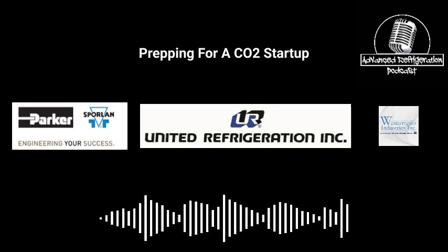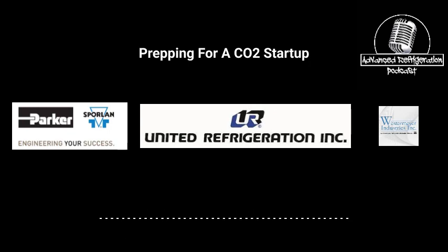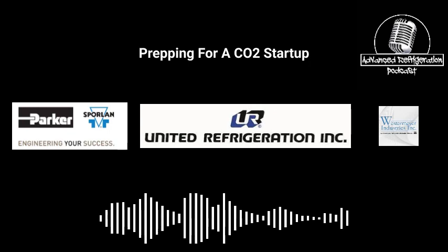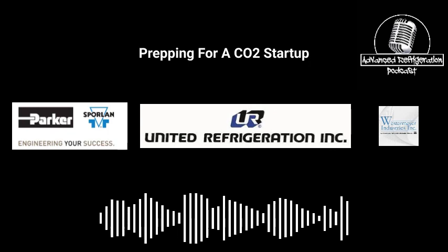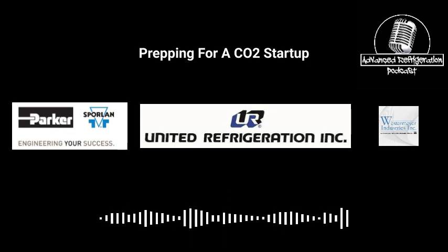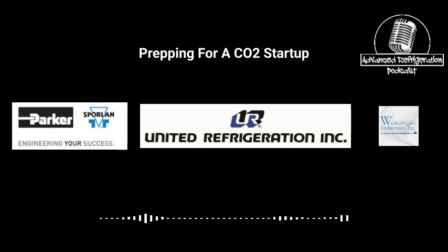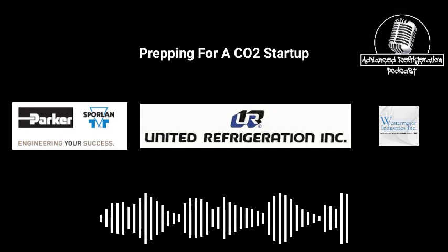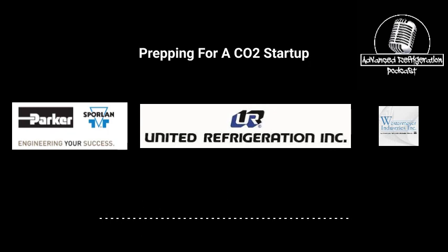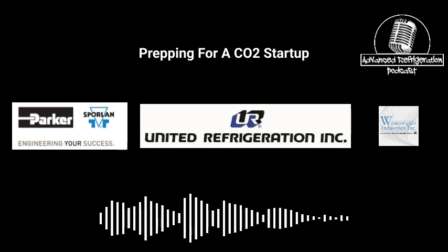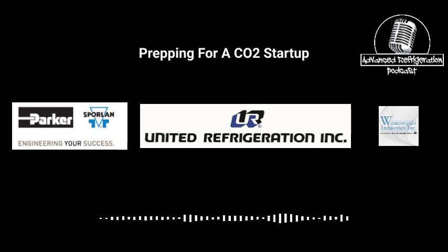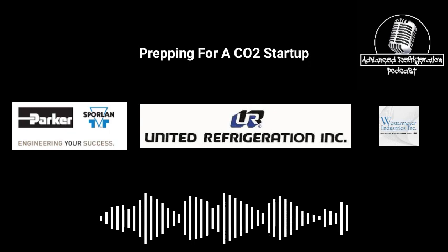Now I want to get all the case controllers on because I want the pulse valves on. I want as much equalized flow through this thing as possible, with as little resistance in the vacuum pump as possible. I don't care if they're all set up or working properly. I just want them powered up and clicking so those pulse valves are going. While this thing is pulling a vacuum, stop looking at it, because it'll make you go crazy and it goes slower if you look at it, no matter if it's tight or not.